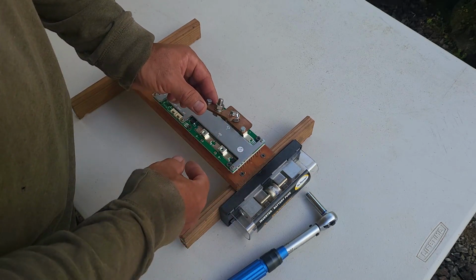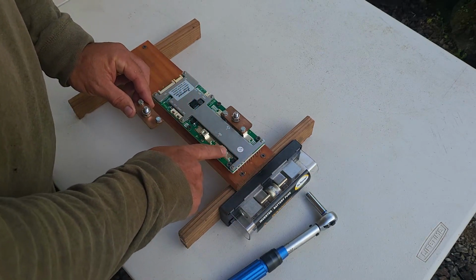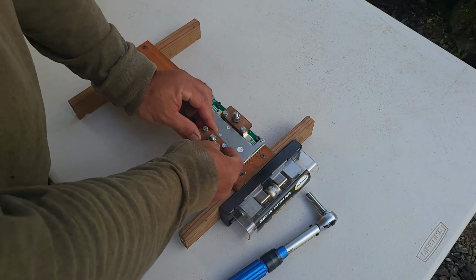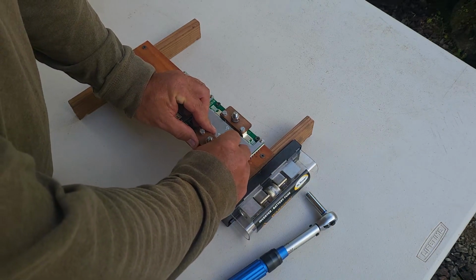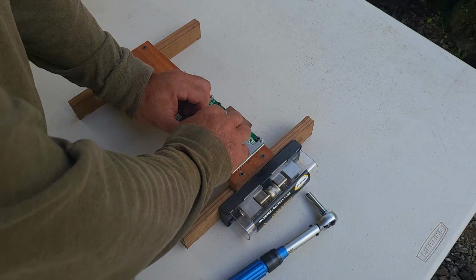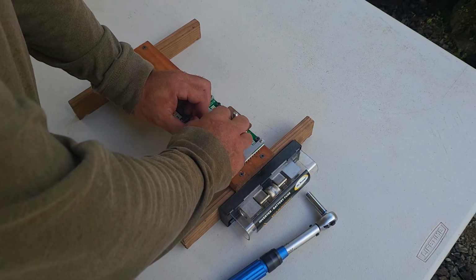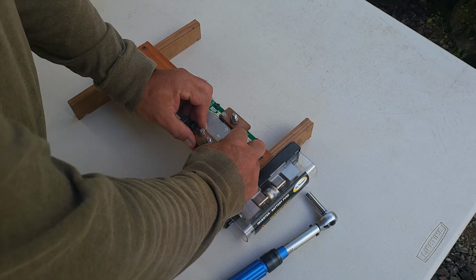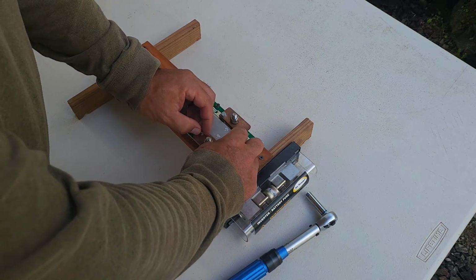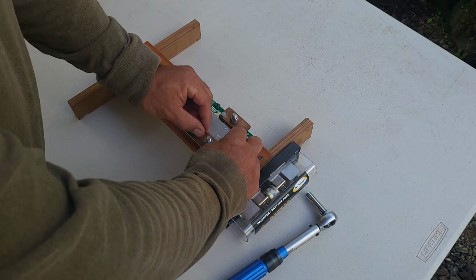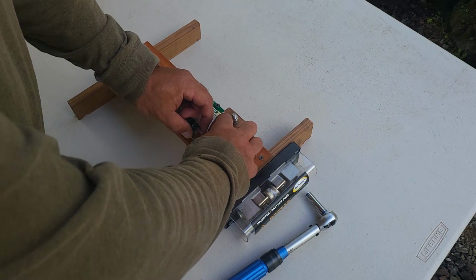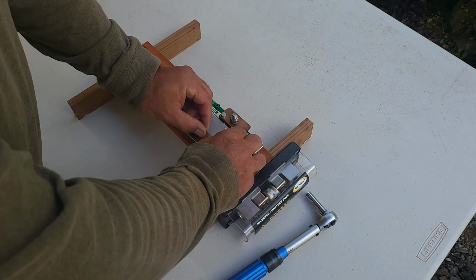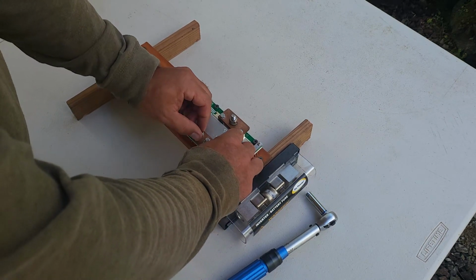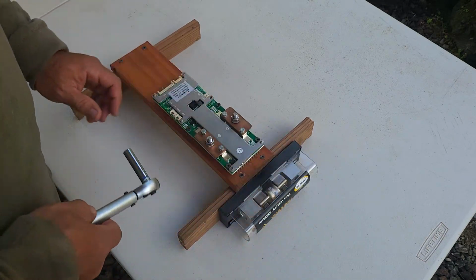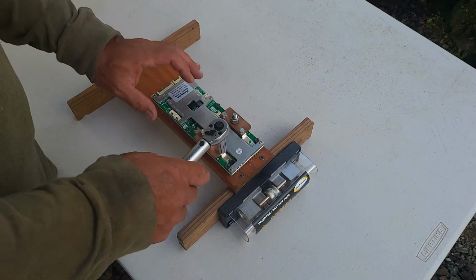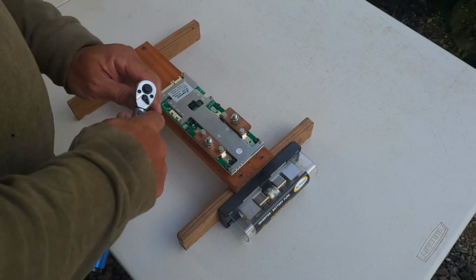These two terminals each split the carrying capacity of the BMS, which is 200 amps, so they're up to 100 amps each. What I'm doing is jumpering them at this point so I can use one larger stud and one larger gauge wire instead of multiple smaller wires. It just depends on how you want to do it, but I felt like this was a little more secure and stable of a setup.